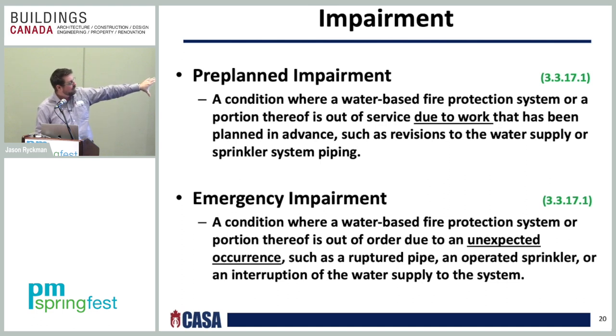The emergency impairment is like it says: it's an emergency. Something happens to your system. You have an activated sprinkler for some reason. That is an emergency impairment, and ultimately, you need to call 911. So if you have an emergency impairment, you need to call 911. No ifs or buts about it. The fire service needs to be aware of that, because ultimately there's something going on: the sprinkler system has been activated.